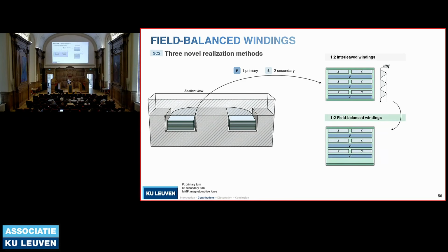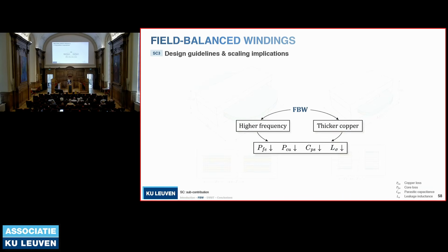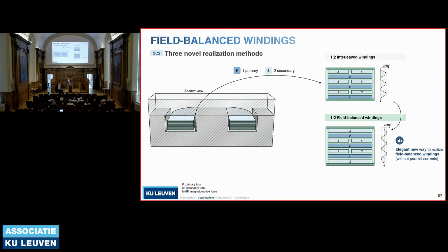Now, how to turn this into a field balance structure? We just duplicate it, add an empty layer at the bottom, and move that secondary from the top to the bottom. This way, the 2 outside layers have half the current of all the inside layers, and we get the magnetic field distribution we're after. It's a very easy, elegant, and unique way to achieve field-balanced windings without relying on specialized winding structures or parallel currents, as is the case in all the prior art.